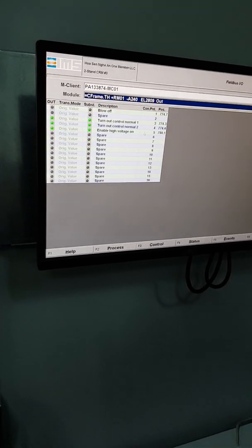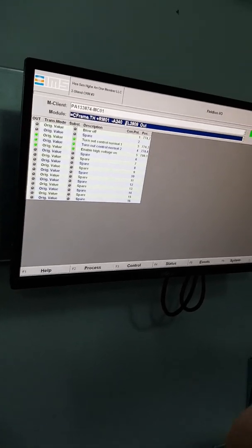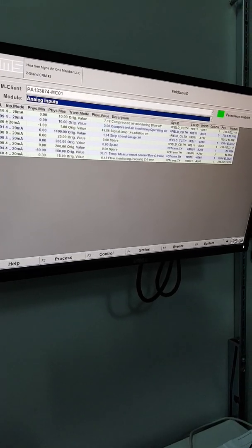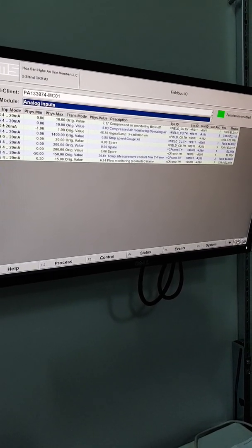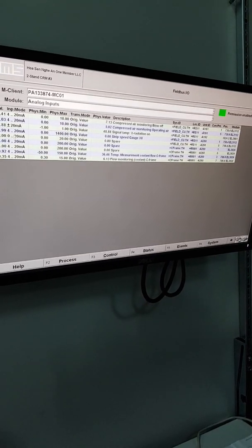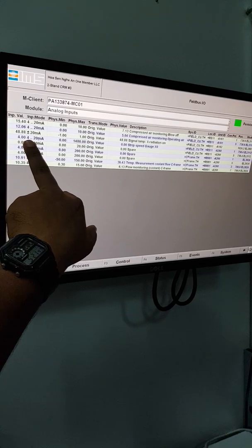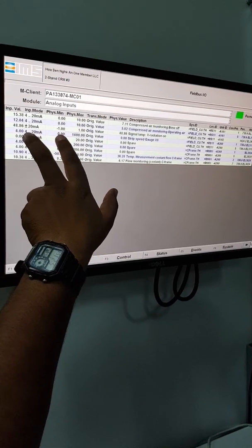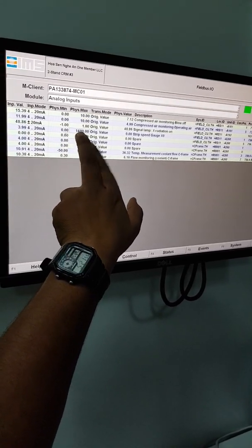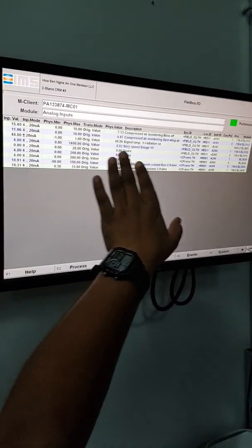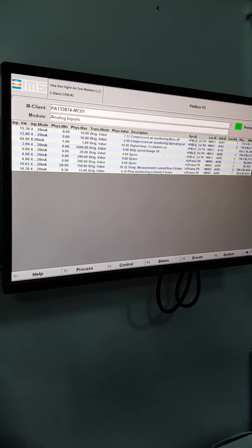Understand? Okay. So inside, the RM is this. Now here is the analog input. You see, in the analog input, we are only getting the strip speed, this one. Yes. This thing we are getting. Okay. We are getting an input of 4 to 20 milliampere, and the scale is 4 equals 0, 20 means 1400. 1400 is your maximum line speed, I think. Yes. This we are getting from where? From SMS. Okay, this is only an analog unit.